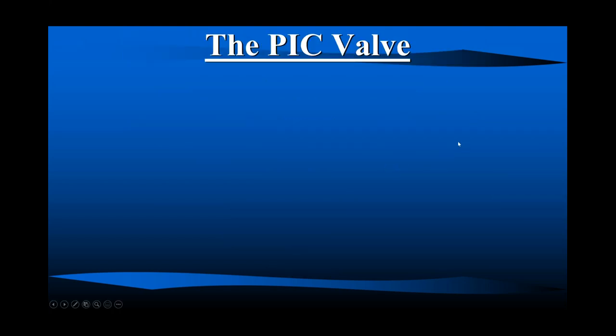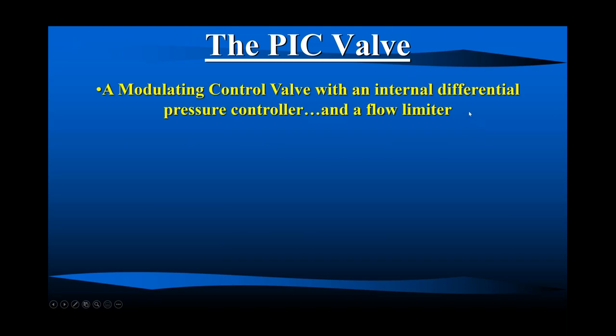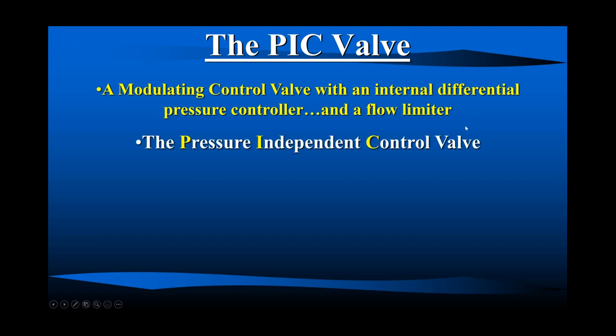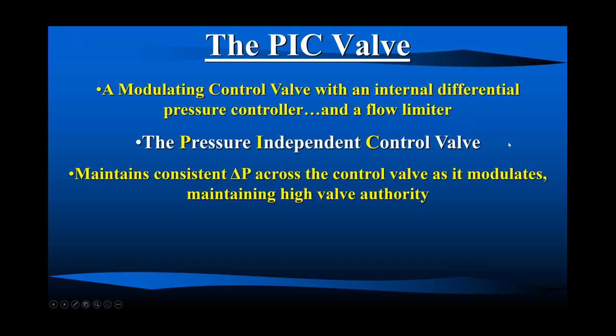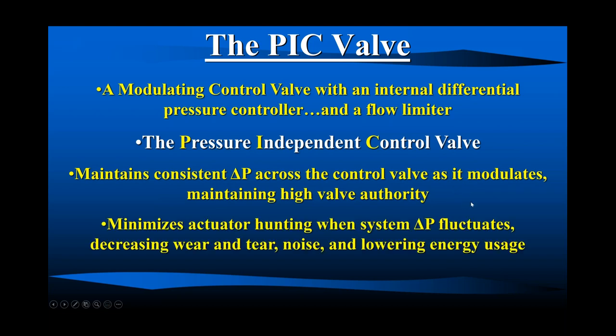So that's why the PIC valve is a modulating valve with an internal flow limiter. It reacts immediately to that changing pressure differential and doesn't allow that coil to put out more or less output than it needs and change the zone temperature, even for a small amount of time. It's that important. So yeah, that's the PIC valve. That's what that does.